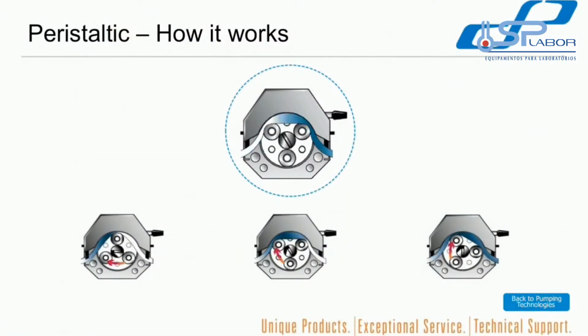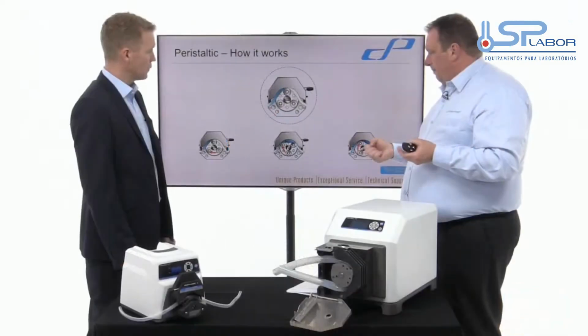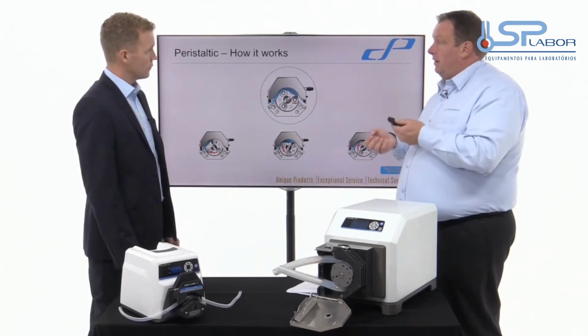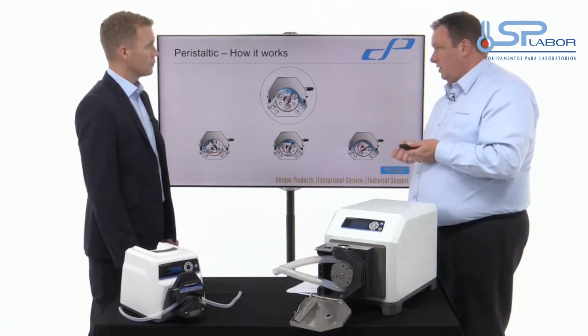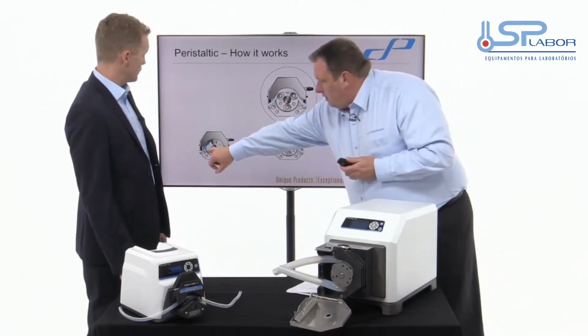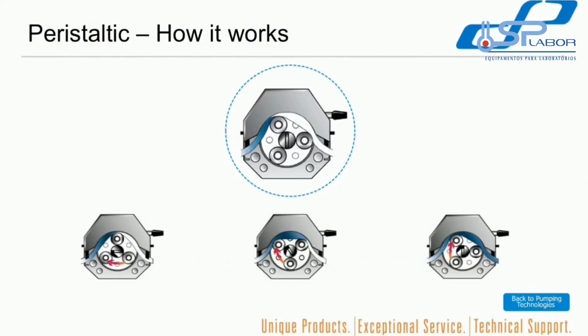What we have is 3 rollers on this particular pump head. Each roller is coming round and squeezing the tube, moving along and releasing. So you're creating pockets, a pocket of liquid within the tube. We defined in another presentation the liquid as being anything from water to toothpaste and many variations in between. The roller has to roll on the tube to move it along, so it's a positive displacement pump. This technology positively displaces or moves one slug of liquid each time. So each rotation of that head moves 3 slugs of liquid. Those 3 slugs of liquid are 1 rotational displacement.